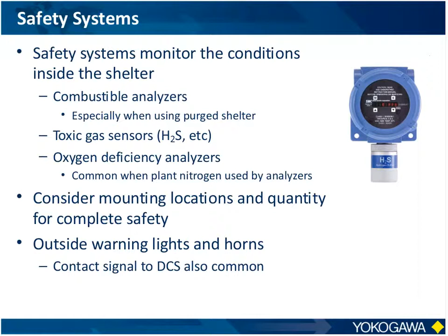And in many situations, it's advisable to wire the alarm system such that if there is an unsafe condition, it'll trigger a warning light and a horn mounted above the entry door. That way, on the outside, personnel know whether it's safe or not safe to go inside. And some will even send a contact closure to their own plant safety systems, with their distributed control system.